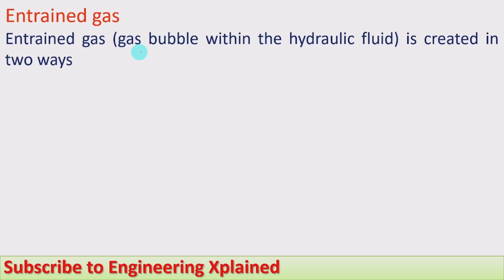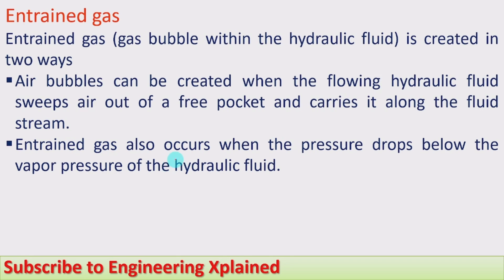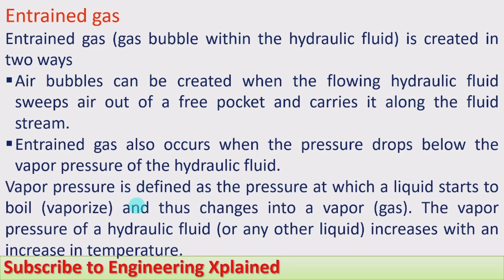The next type is entrained gas. A gas bubble within the hydraulic fluid is created in two ways. Air bubbles can be created when the flowing hydraulic fluid sweeps air out of the free pocket and carries it along with the stream. Entrained gas also occurs when the pressure drops below the vapor pressure of the hydraulic fluid, causing vaporization of the fluid and forming entrained gas.